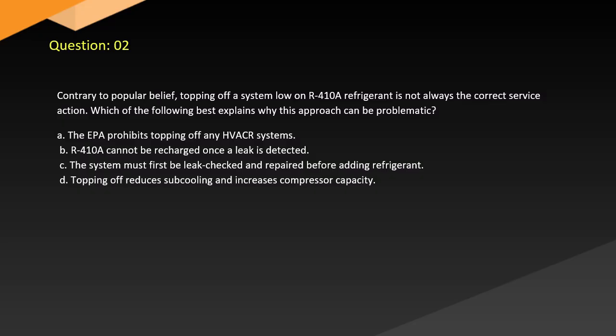Question 2. Contrary to popular belief, topping off a system low on R-410A refrigerant is not always the correct service action. Which of the following best explains why this approach can be problematic? A. The EPA prohibits topping off any HVACR systems. B. R-410A cannot be recharged once a leak is detected. C. The system must first be leak checked and repaired before adding refrigerant. D. Topping off reduces subcooling and increases compressor capacity.